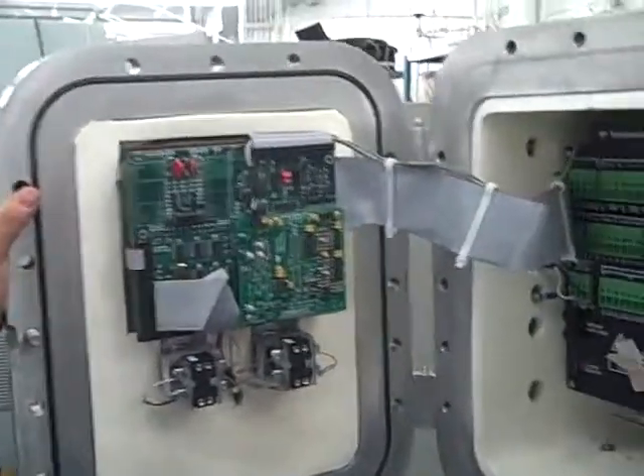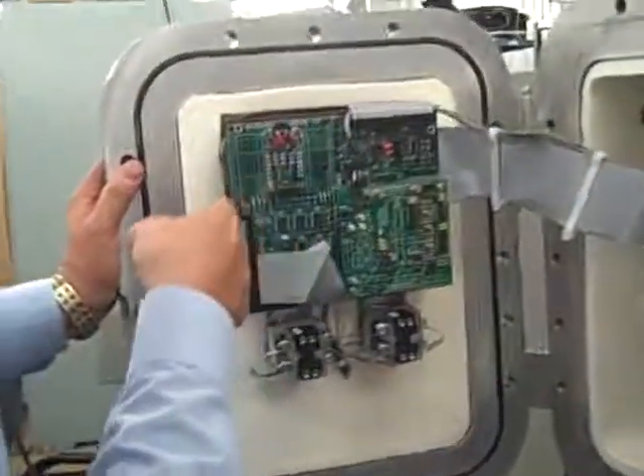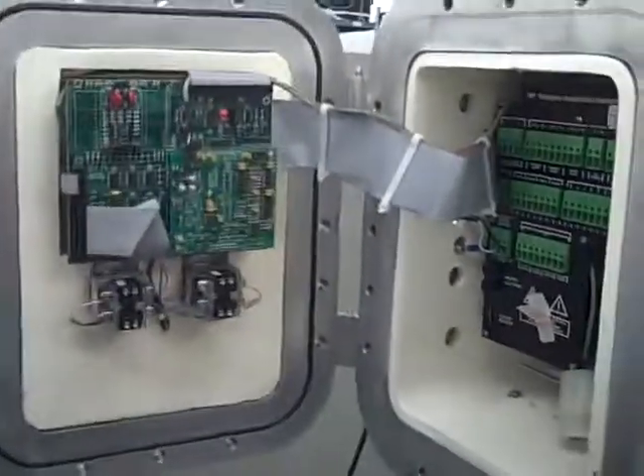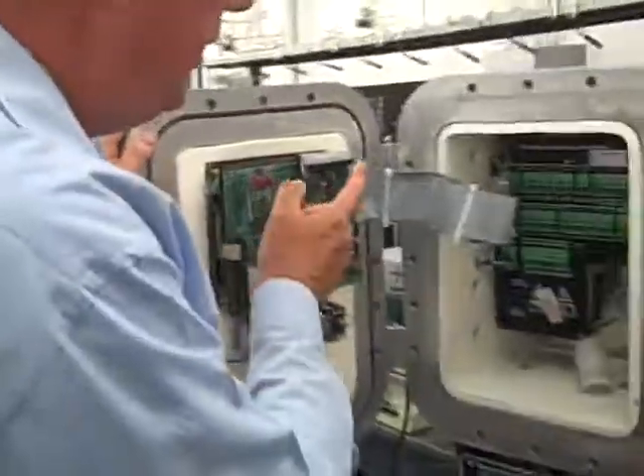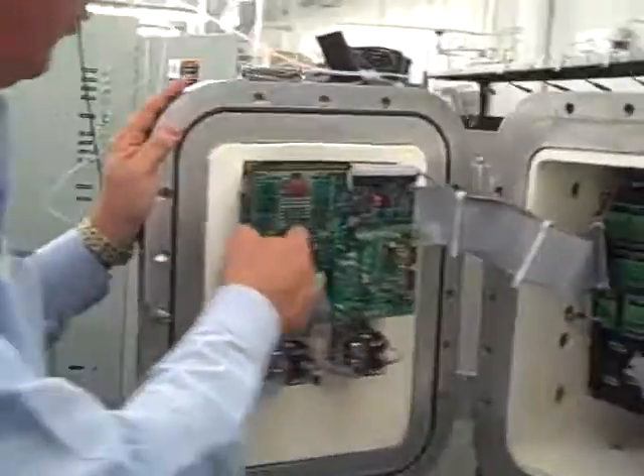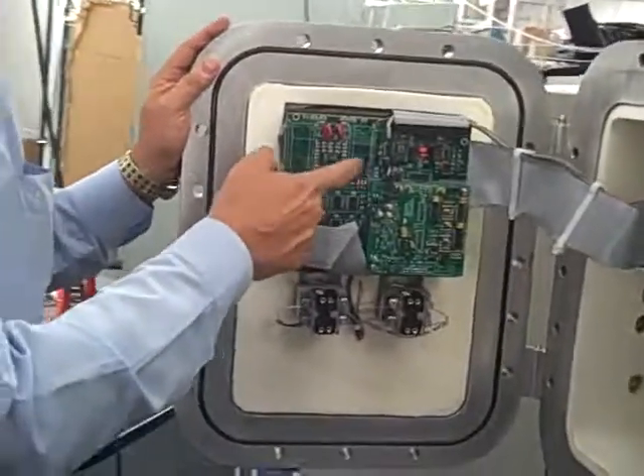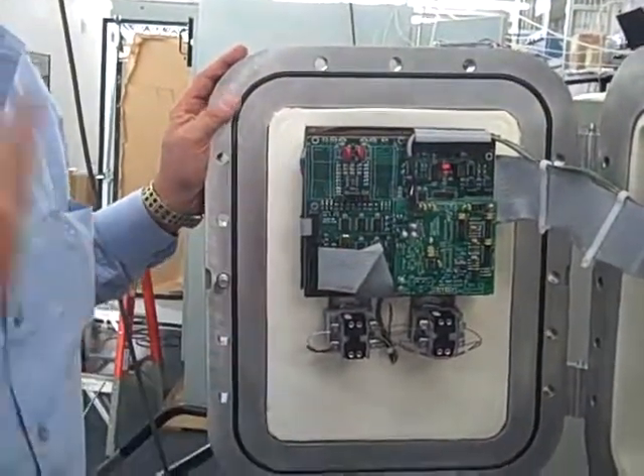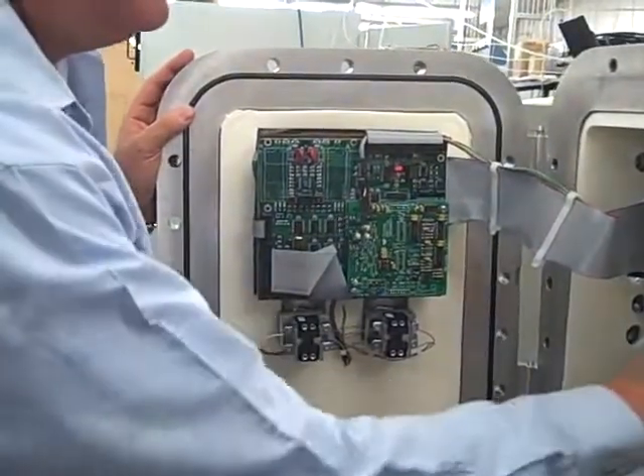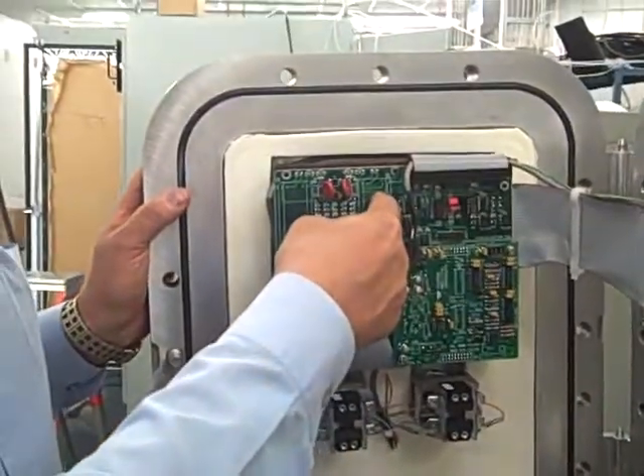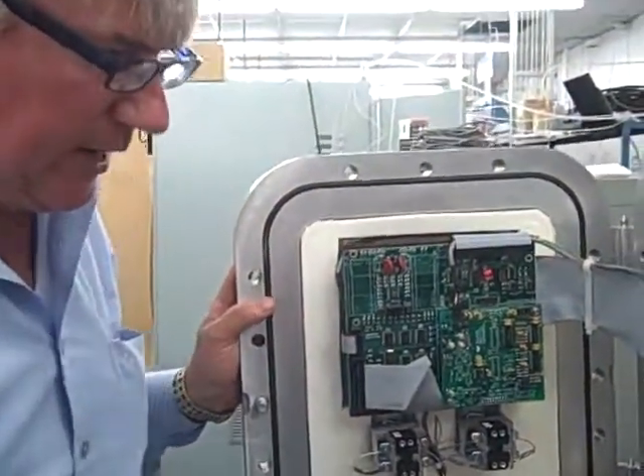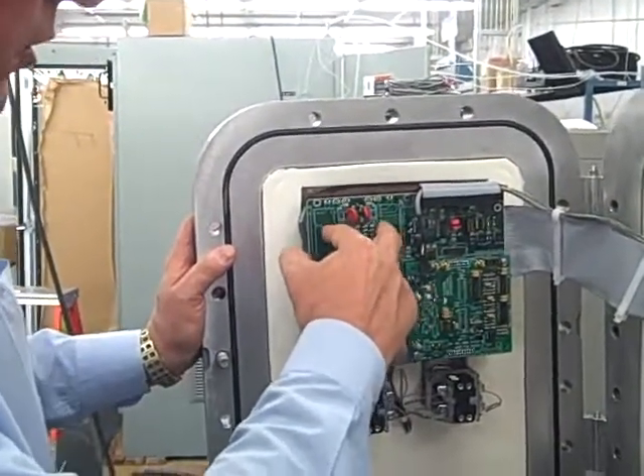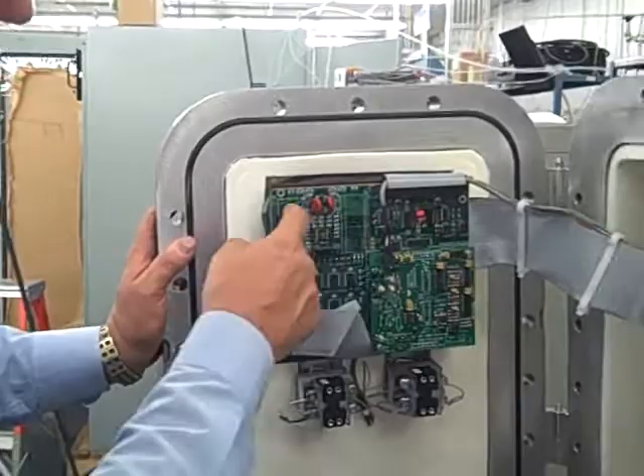Oh, no 4 to 20, yeah, this unit has no 4 to 20. Oh, that's peculiar. Should have some 4 to 20s. Oh, that's right, that's a good point. My colleague has mentioned that the P unit in some cases is ordered without 4 to 20 milliampere outputs. So that's what this one has. There's no 4 to 20s in it. That's a sales adding option. For the T units, the percent of range comes standard, and if you want the range indicator, it's extra. This particular unit, as you can see, has no modules mounted here. These were the modules where the 4 to 20 milliamps go. So thank you for mentioning that.